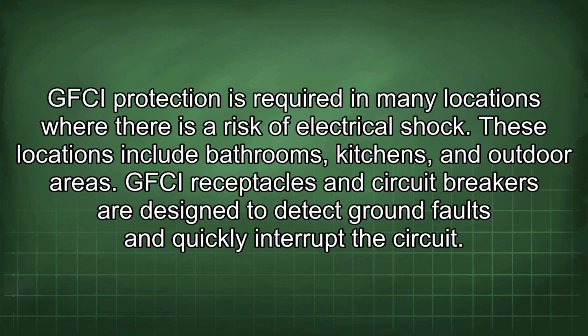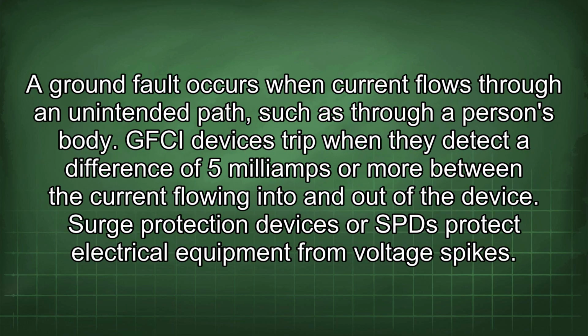GFCI protection is required in many locations where there is a risk of electrical shock. These locations include bathrooms, kitchens, and outdoor areas. GFCI receptacles and circuit breakers are designed to detect ground faults and quickly interrupt the circuit. A ground fault occurs when current flows through an unintended path, such as through a person's body. GFCI devices trip when they detect a difference of 5 mA or more between the current flowing into and out of the device.